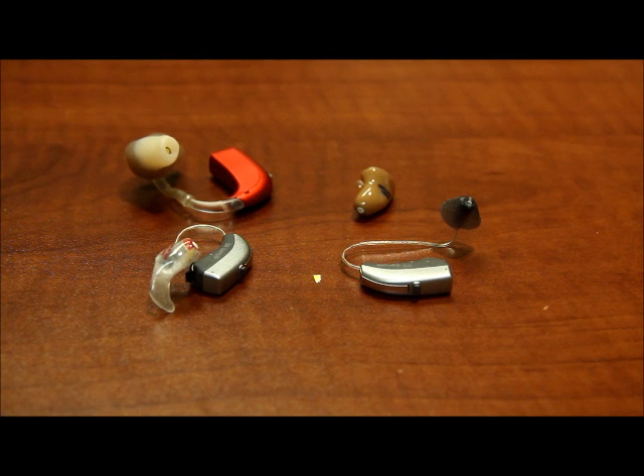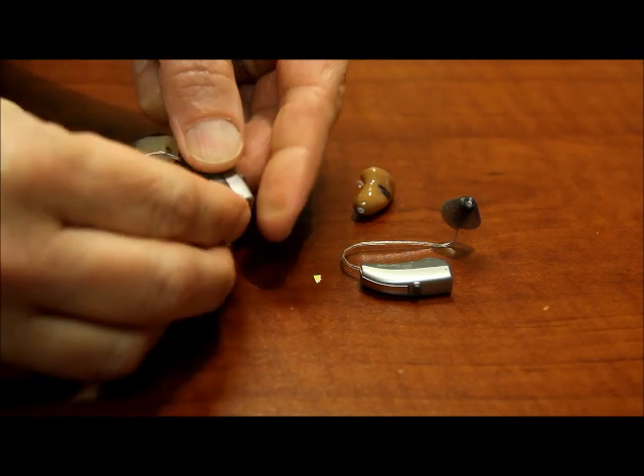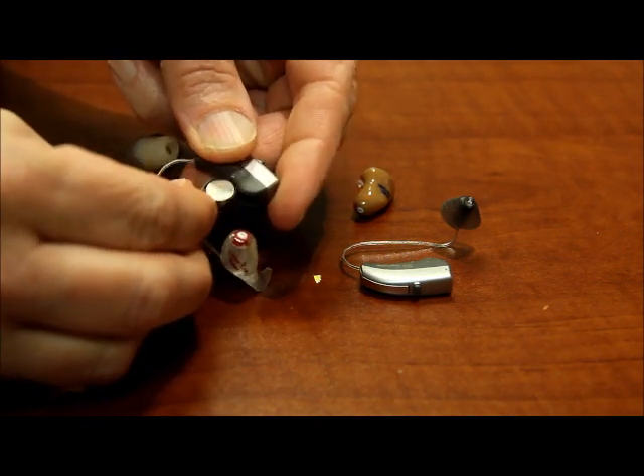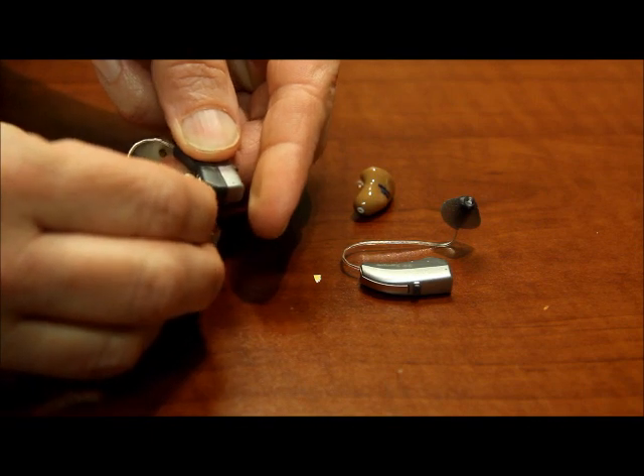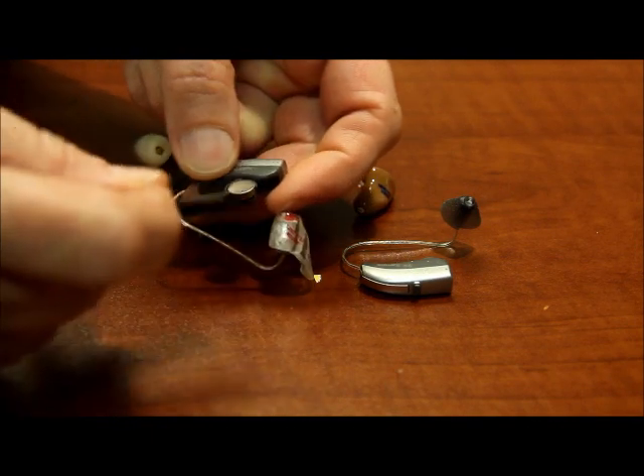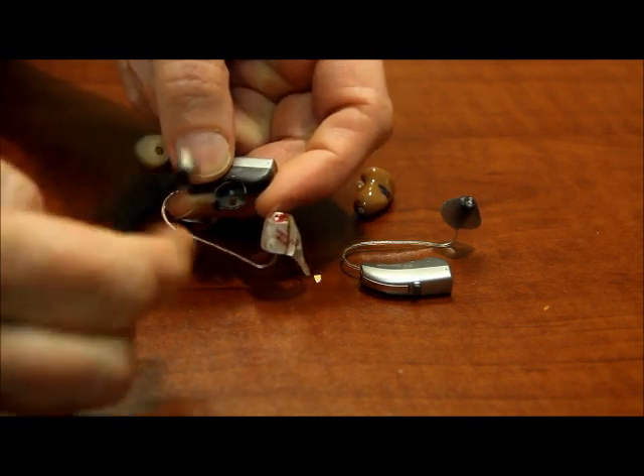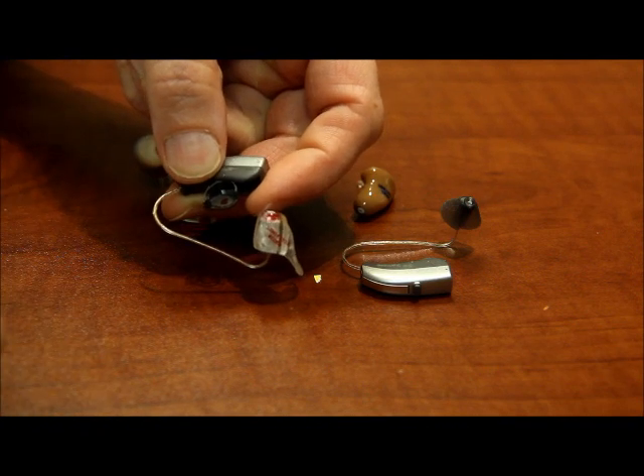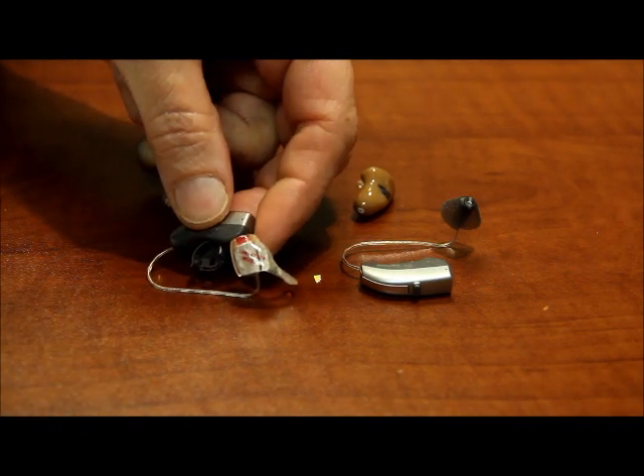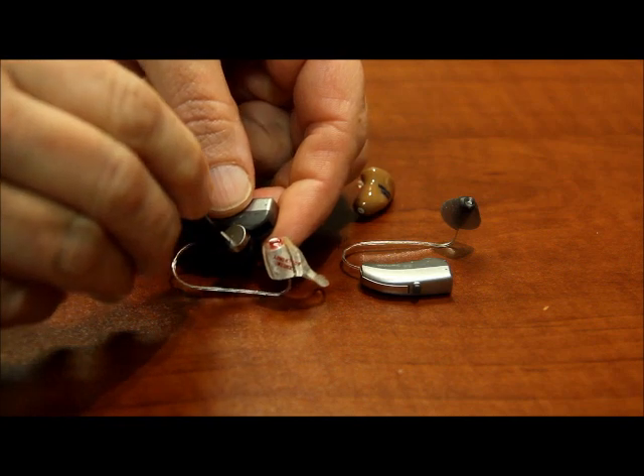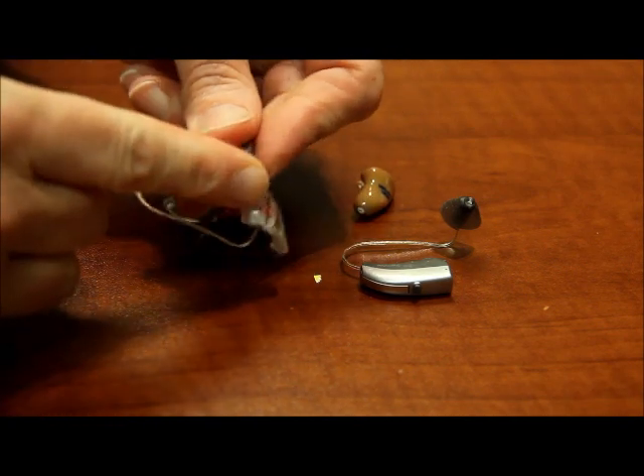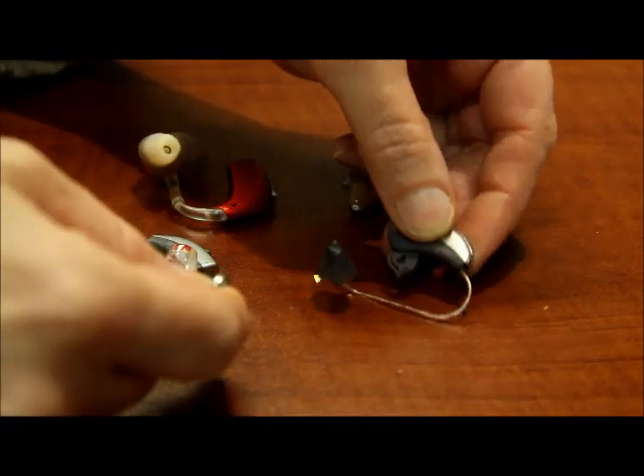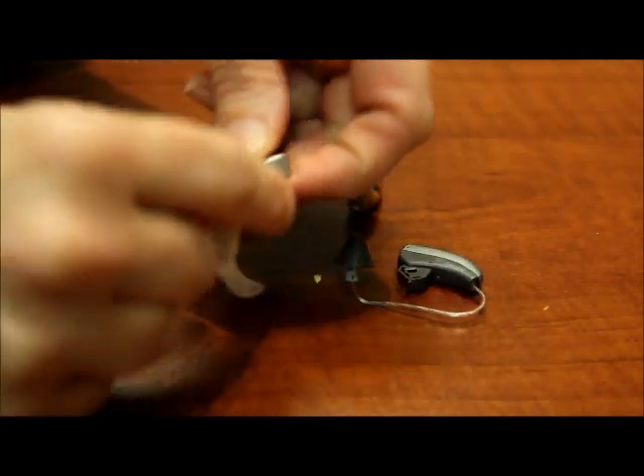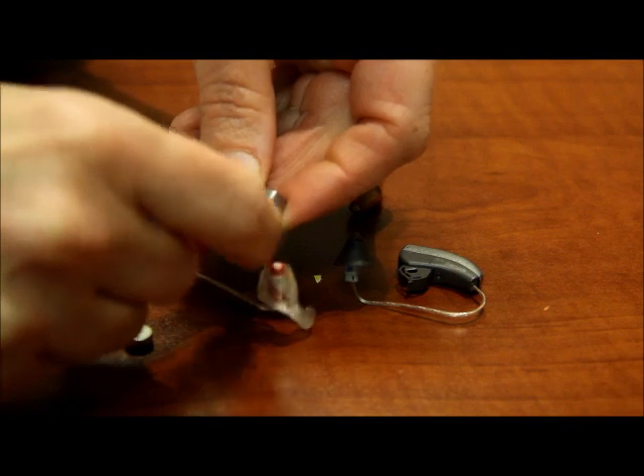The first thing to check is the battery. Sounds obvious, but it's the easiest thing to do. The first thing that you want to do is replace the battery with a known fresh battery. If you don't have a battery that you know is good, a good thing to do would be to switch the batteries between the hearing aids. If you have one hearing aid that's working and one that is not, change the batteries between them. If that changes the problem from one hearing aid to another, you know that it's probably the battery.